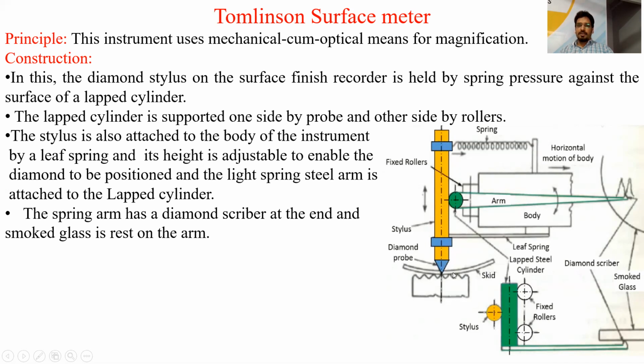There is a stylus present in the Tomlinson Surface meter, and this stylus has a diamond probe which is to be moved on the surface whose roughness is to be measured. In this, the diamond stylus on the surface finish recorder is held by spring pressure against the surface of a lapped cylinder. This stylus is kept vertical with the help of two springs. One is the helical spring and the other is the leaf spring. A leaf spring and a helical spring are connected to the body of the Tomlinson Surface meter. So this stylus can do vertical motion, either in the downward or the upward direction.